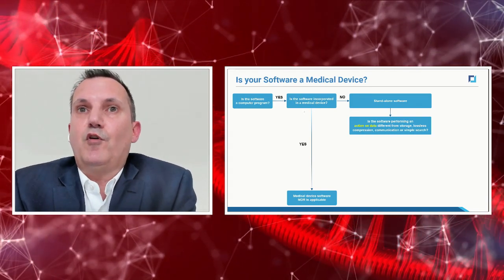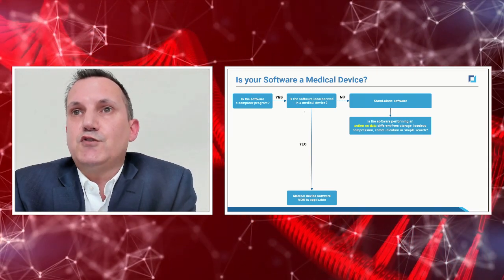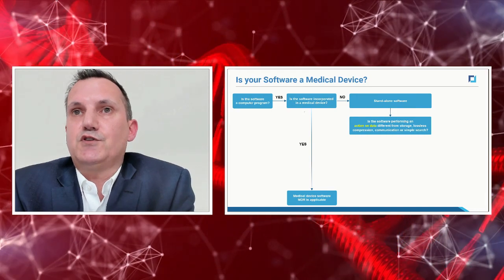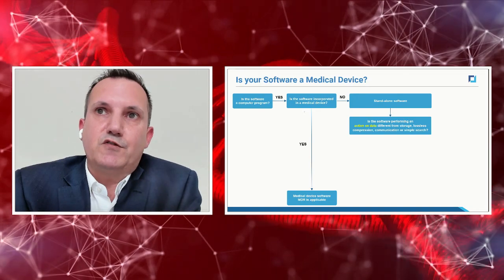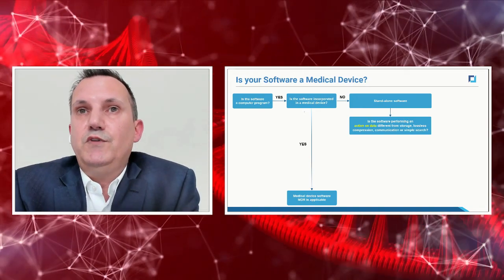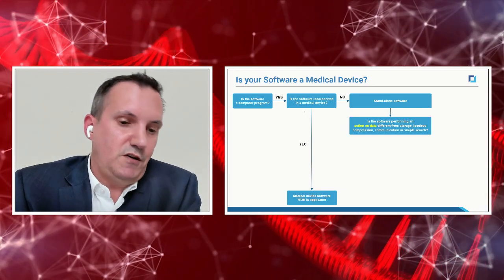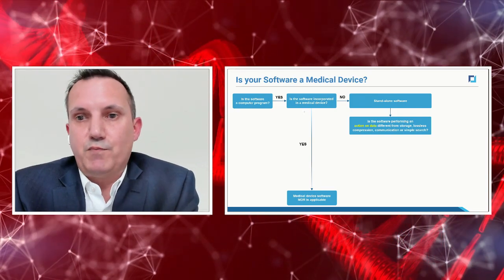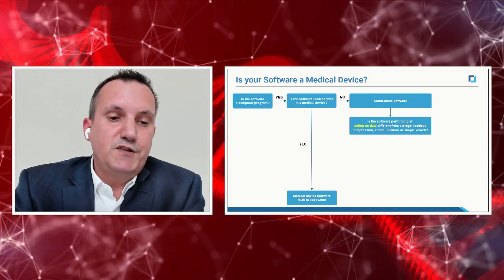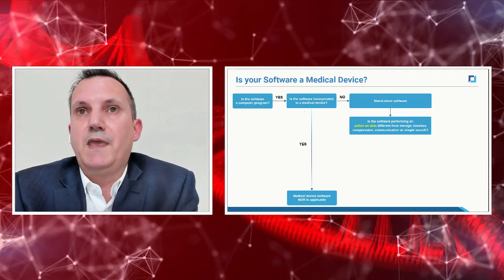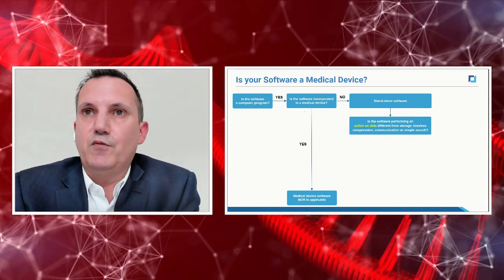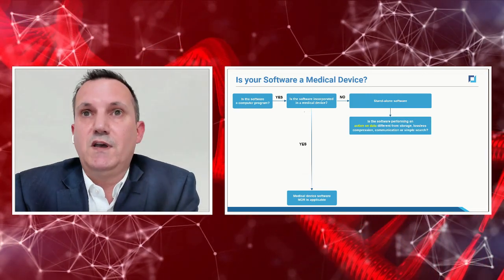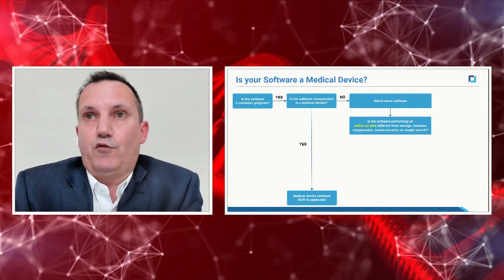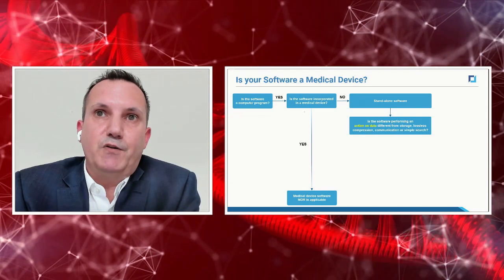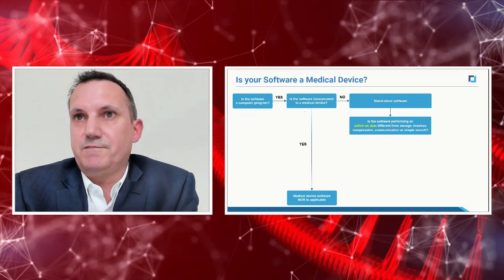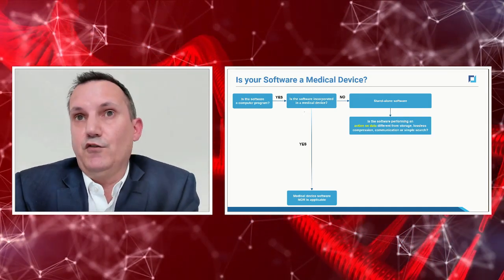The first criterion: is the software performing an action on data that is different from simple storage, lossless compression, communication, or simple search? So one of the criteria is that, to be a medical device, your software needs to perform an action on data. If you have, for instance, a textbook for educational purposes, even if it's a medical textbook, it will not be considered a medical device because there is no action on data. If we think back on the earlier example, the health information system storing and managing electronic medical records, there also only data is stored. Of course, there might be a search function, but there is no real action on the data itself. The data itself is not processed. So in that case, the example I gave earlier is not a medical device.